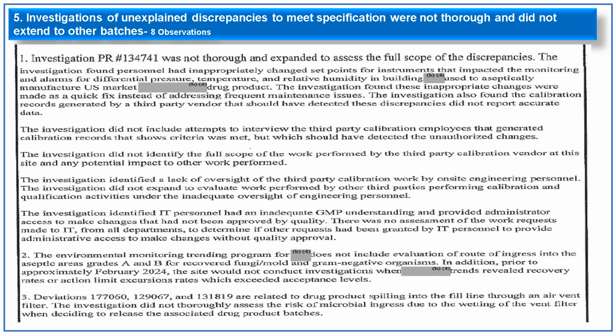The investigation found that these inappropriate changes were a quick fix instead of addressing the frequent alarms. The investigation found out that calibration records generated by the third-party vendor did not detect these discrepancies and did not report the accurate data. So the investigation did not include attempts to interview the third-party calibration vendor that generated these calibration records.